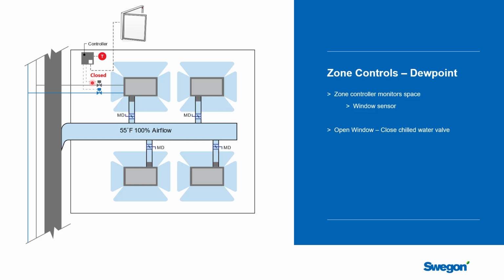It's not a good idea to be running your air conditioning at the same time you're opening your windows. The occupant really needs to choose which way they want to do it. They have the best idea of what's going to make them the most comfortable in the space, and if they want the windows open, that's great. But we're going to shut the air conditioning system down until they close the windows. So the moment that window switch opens, that would be the signal for the controller to shut off the chilled water valve.